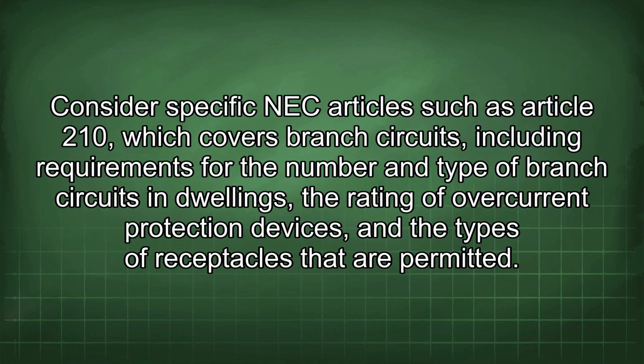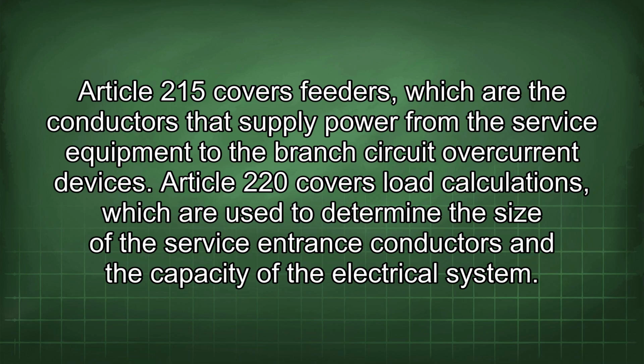Consider specific NEC articles such as Article 210, which covers branch circuits, including requirements for the number and type of branch circuits in dwellings, the rating of overcurrent protection devices, and the types of receptacles that are permitted. Article 215 covers feeders, which are the conductors that supply power from the service equipment to the branch circuit overcurrent devices. Article 220 covers load calculations, which are used to determine the size of the service entrance conductors and the capacity of the electrical system.